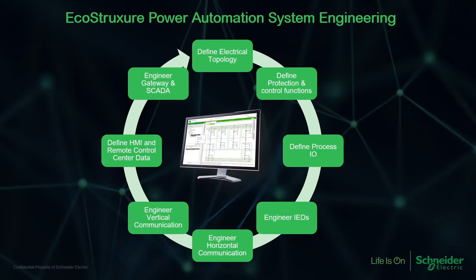The software allows the users to define the electrical application, define the protection and control functions to meet the needs of the application, define the process I/O, and engineer the IEDs from the system configuration tool perspective. It can configure horizontal communication, that is GOOSE, reports, and engineering vertical communication on sampled values, configuration from gateways to SCADA on protocols like IEC 104 and Modbus, and also integrate data coming from Modbus to proxy gateways, gateway configuration compliant with 90-2, as well as mapping supported on 80-1.